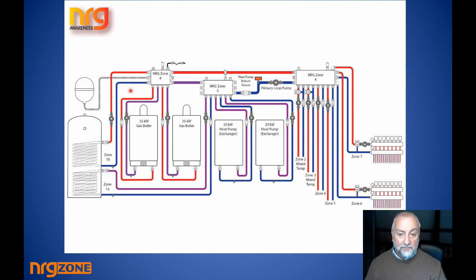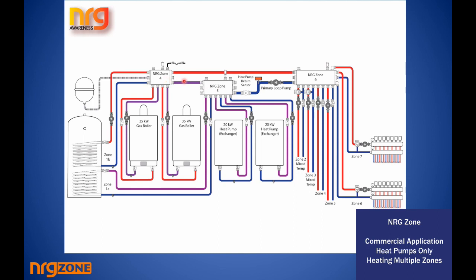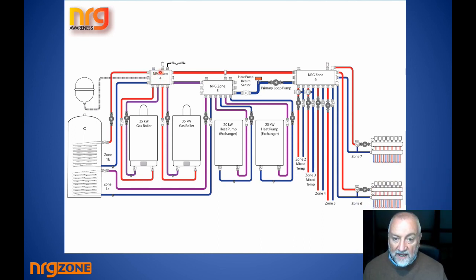If in the meantime you want to have the heat pumps preheat the heating water, the heat pumps fire up to say 40 degrees and bring it up to 45. The 45 degree water is put in here, drawn down by the gas boilers and taken up to whatever you've decided your delta T is to be. Let's say 70 degrees. Your 70 degree flow is coming out. And now this pump's momentum, pushing water to this enclosed circuit, is pushing the 70 degree water over. So now we've got a full temperature circuit.